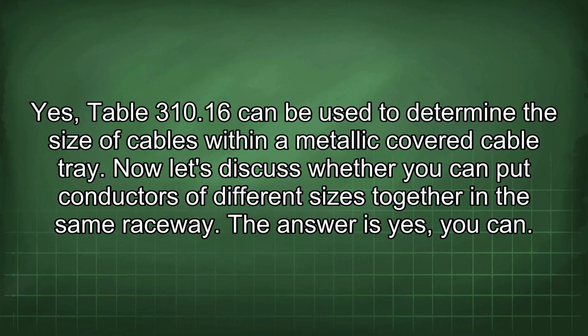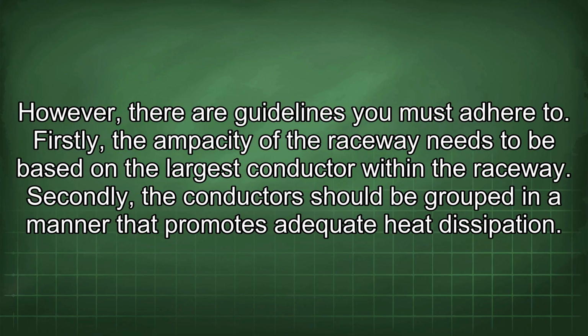Yes, Table 310.16 can be used to determine the size of cables within a metallic covered cable tray. Now let's discuss whether you can put conductors of different sizes together in the same raceway. The answer is yes, you can. However, there are guidelines you must adhere to.